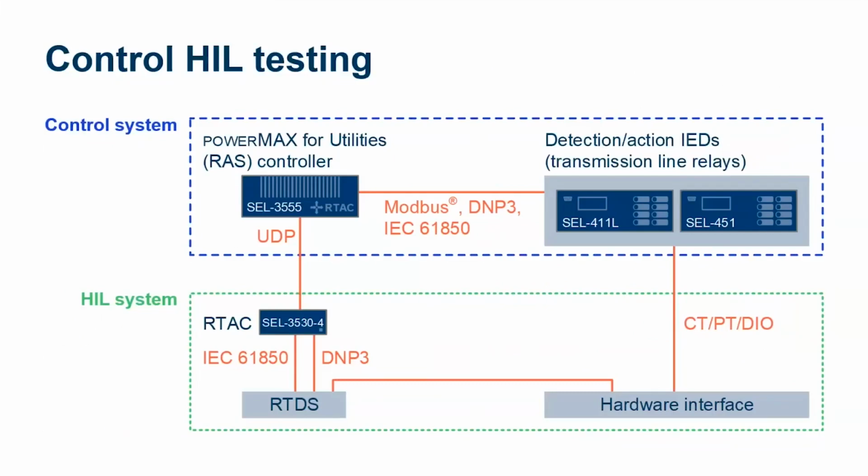This setup allows us to simulate operational contingencies such as N-1s, N-2s, or closely timed contingencies, and study how the RAS will help when subjected to these outages. This setup also helps us to run free-form cases. If any abnormalities are found, they are addressed before taking any further steps.